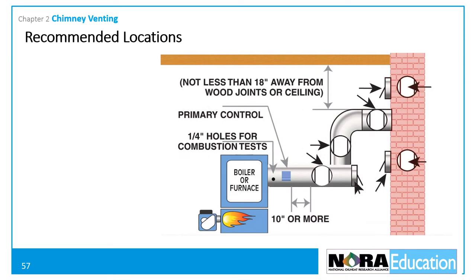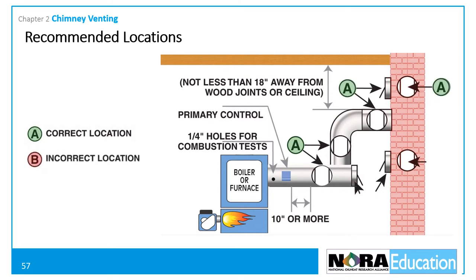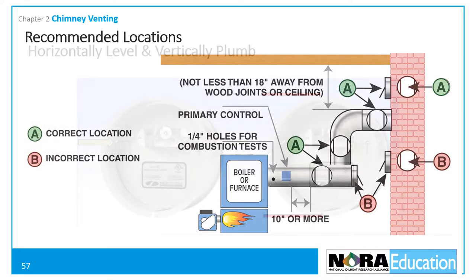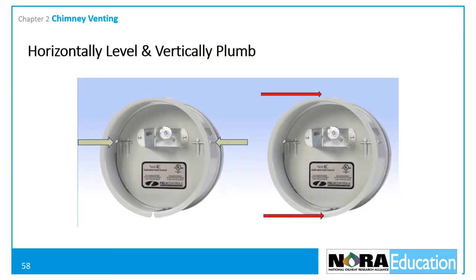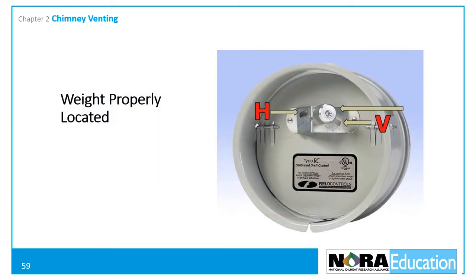There are three main requirements regarding draft controls. First, they must be installed in the proper location — in the diagram, locations marked A are acceptable and locations marked B are not. Second, they must be horizontally level across the pivot points and vertically plumb. Third, if the control has specific weight locations for vertical and horizontal installations, the weight must be in the proper location to operate properly. In this picture, the weight is installed in the correct location for a vertical flue.